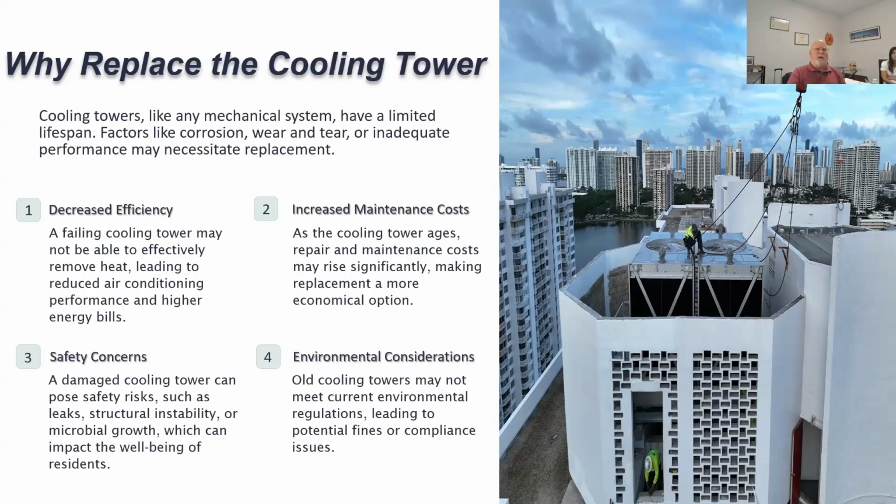But generally for towers that we see here on condominiums, it makes a lot more sense to just pull them off and replace them wholesale after they get to a certain age and increased maintenance cost. You're working on that tower all of the time. One of the things that is kind of covered under maintenance cost is reliability.